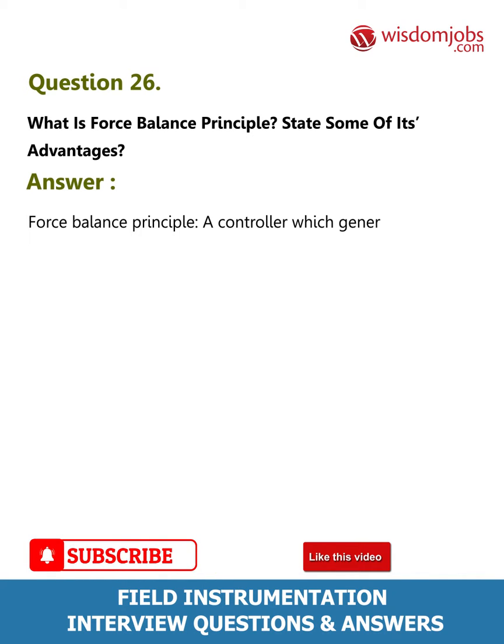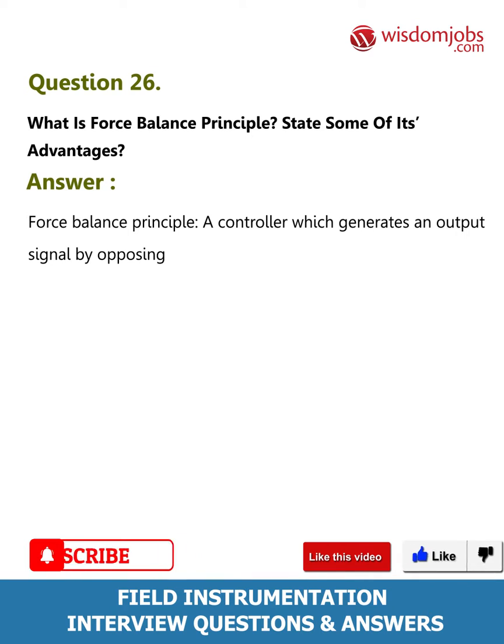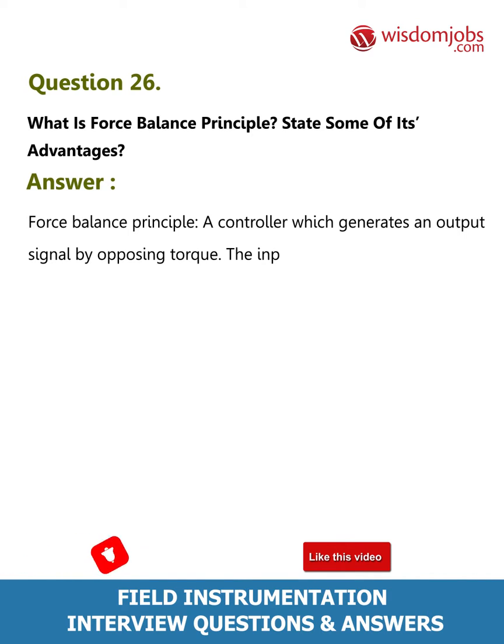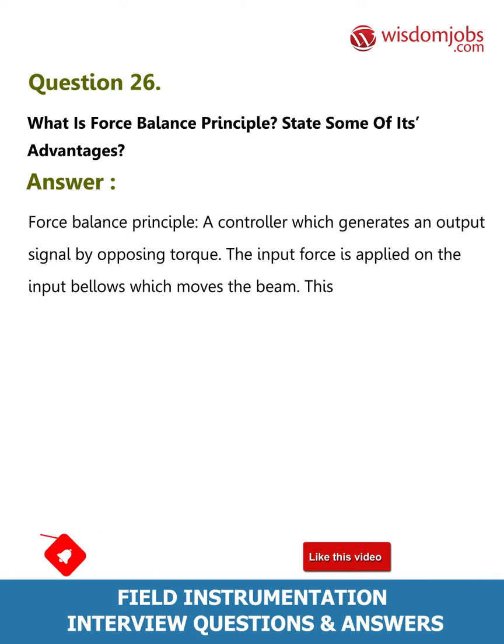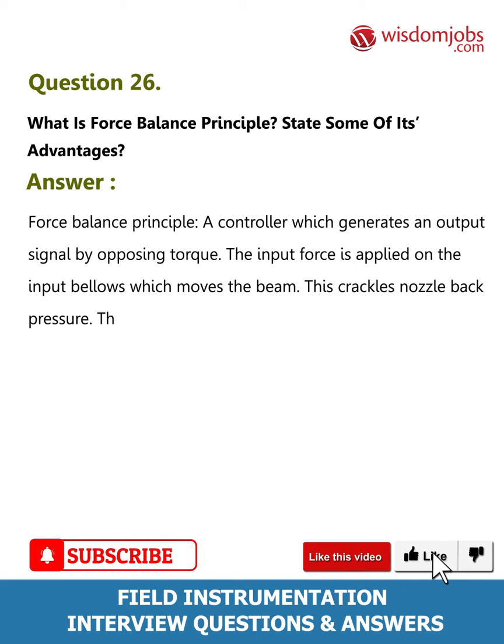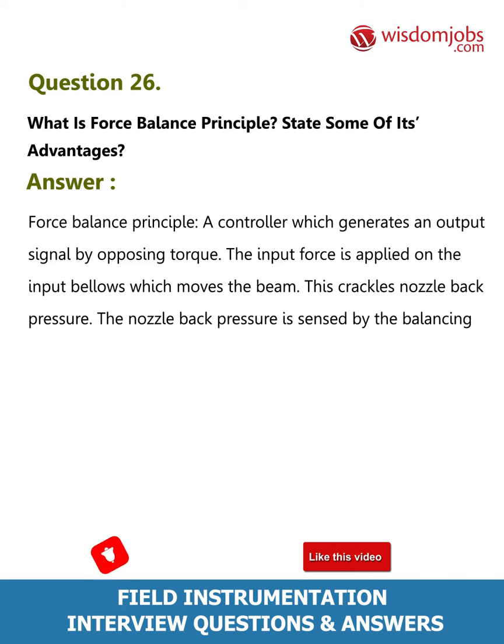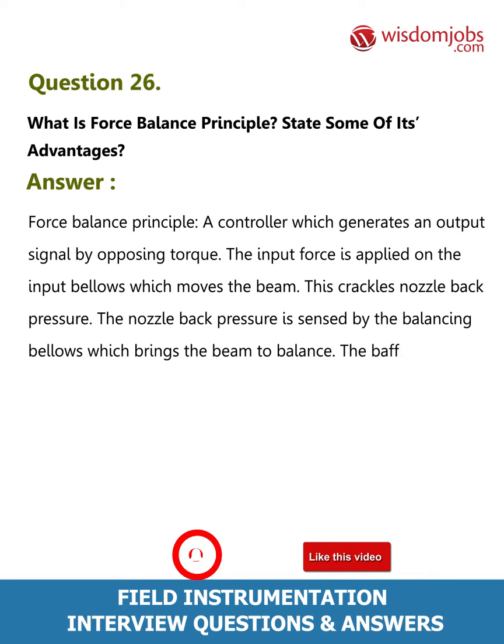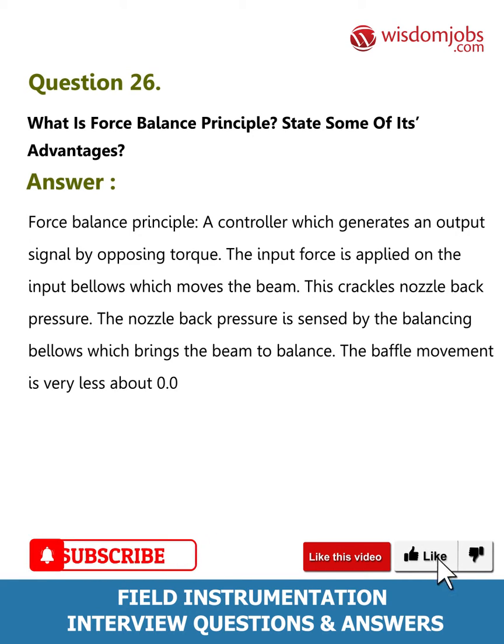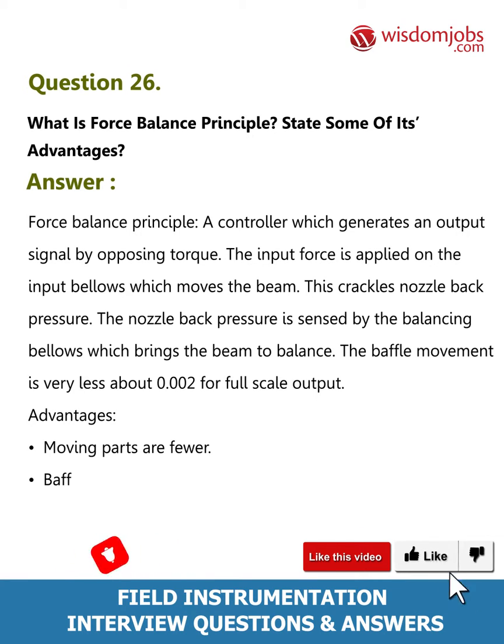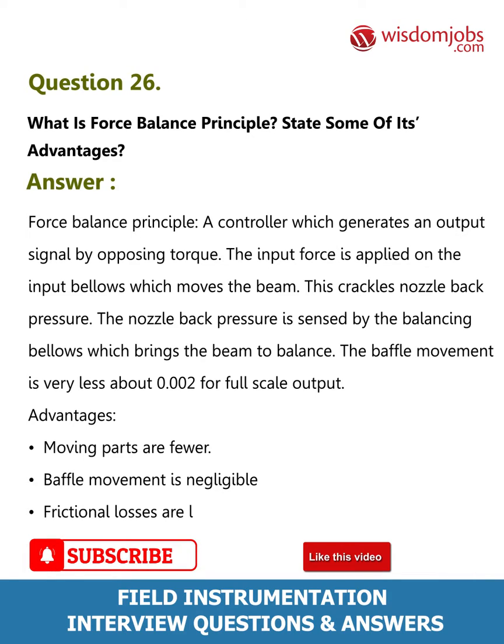Question 26: What is the force balance principle? State some of its advantages. Answer: A force balance controller generates an output signal by opposing torque. The input force is applied on the input bellows, which moves the beam. This changes the nozzle back pressure, which is sensed by the balancing bellows, bringing the beam to balance. The baffle movement is very small, about 0.002 inches for full scale output. Advantages: moving parts are fewer, baffle movement is negligible, and frictional losses are less.